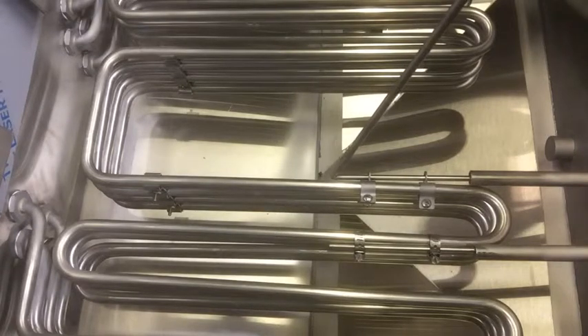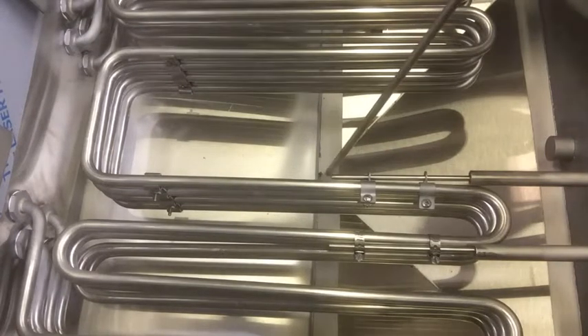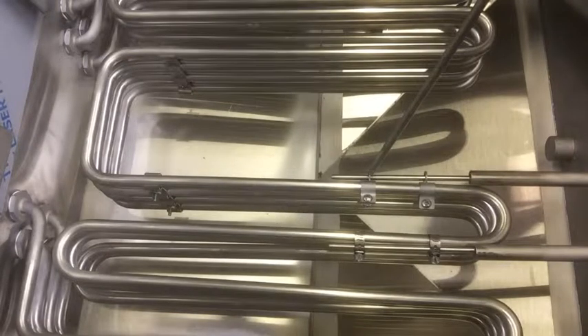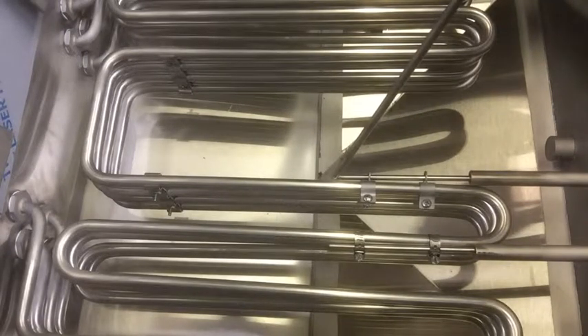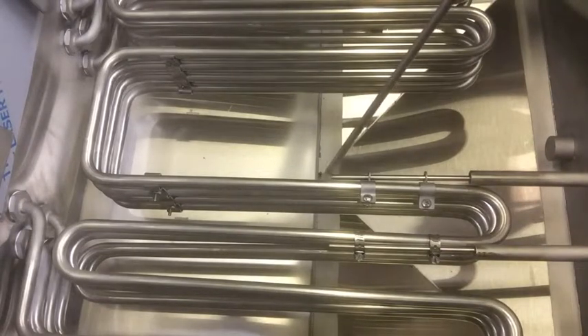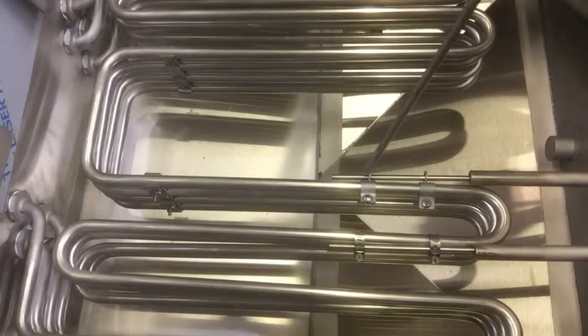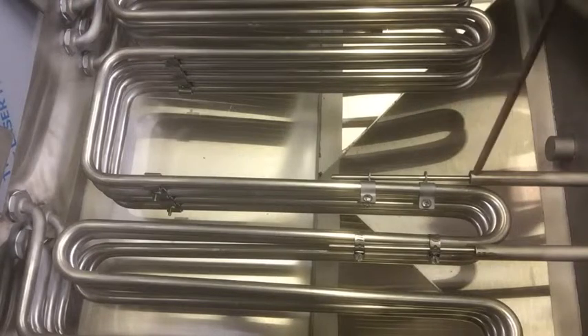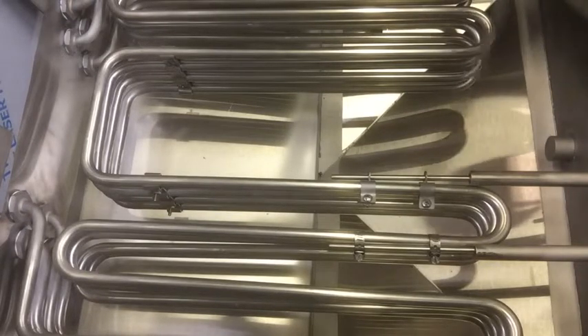And the tip of this probe should be 1.5 inches from this last bracket. So from here to here should be 1.5 inches, 3/16 of an inch between here and the side of the element. So again, 3/16 between the inside edge of the probe and the element, and then 1.5 inches from the tip to this first clamp. And this other is here just to stabilize it. It needs to be somewhere in between.